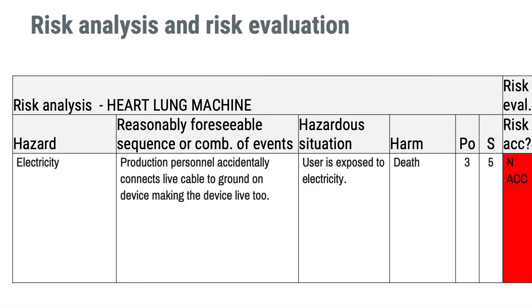For all your medical devices you must do risk analysis. Risk analysis starts with hazards — hazards are potential sources of harm. The next step is to identify reasonably foreseeable sequences or combinations of events that could lead to hazardous situations and harms. When you have done that, you should estimate the risk by determining the probability of occurrence of harm and the severity of that harm. This is the process which in the standard is referred to as risk analysis.